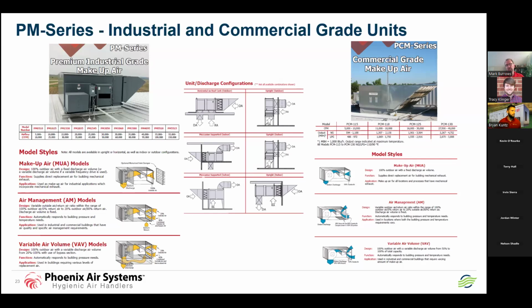So with these, you can see the common styles. We have makeup air, 100% outside makeup air, our air management or AM style, also called 80/20 units, taking that mixed air application that Mark just gave you the lowdown on, variable air volume and fixed recirculated styles as well. As far as configurations go, pretty much anything and everything. It's horizontal to vertical, from indoor suspended, upright indoor, pretty much you name it, we can support it. So want to make you guys all aware of this as well.